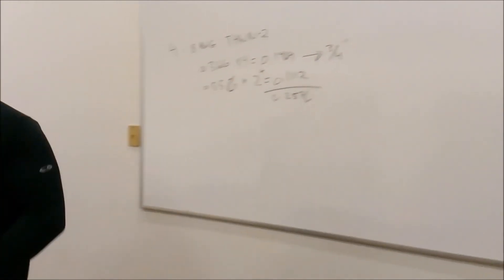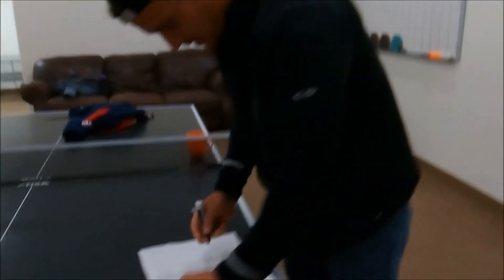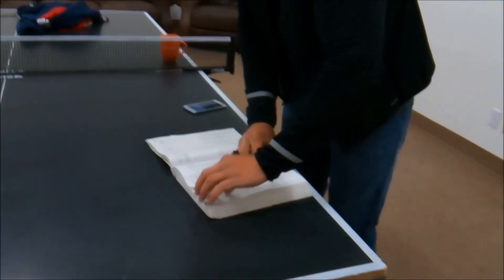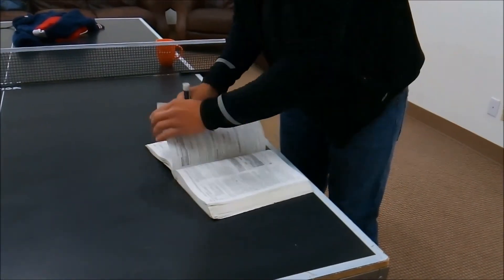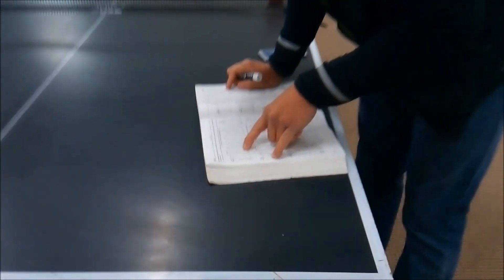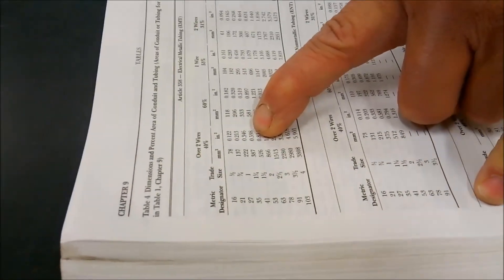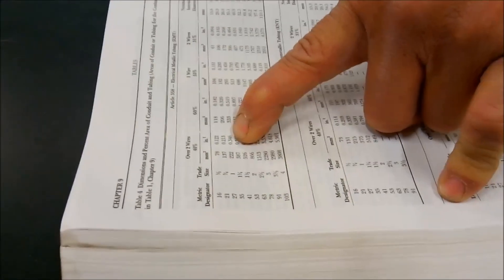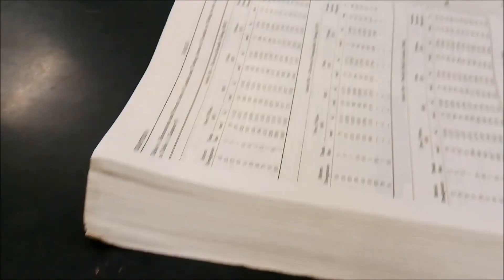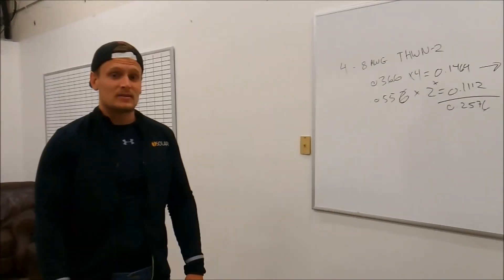And then go back to our EMT table here. And we're looking for an area over 2 wires, so 40% of the area that is equal to .256 or greater. And that looks like we jump up to 1 inch conduit at that point. And that's how you do conduit fill.